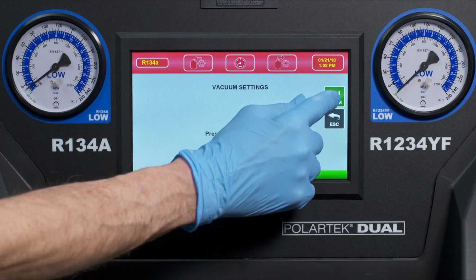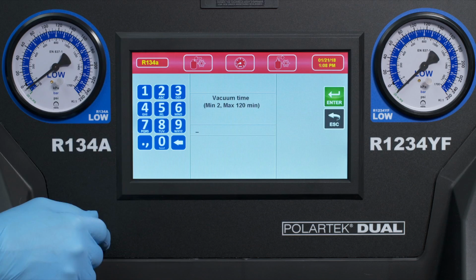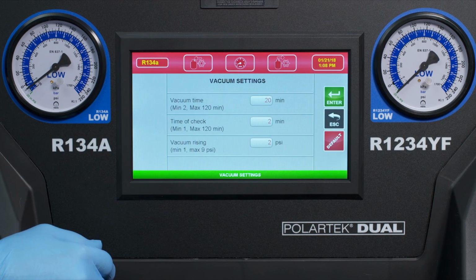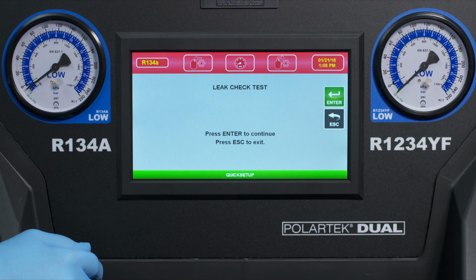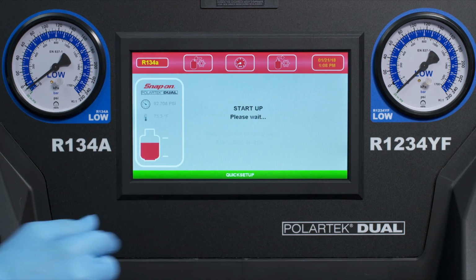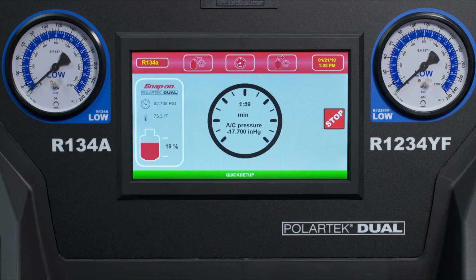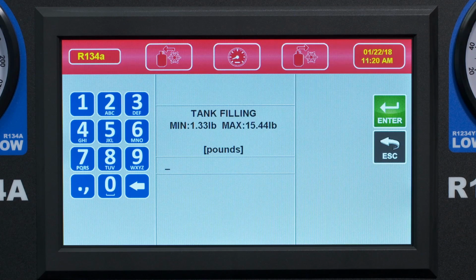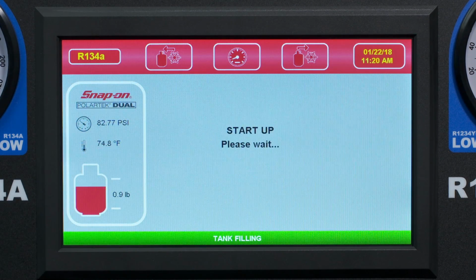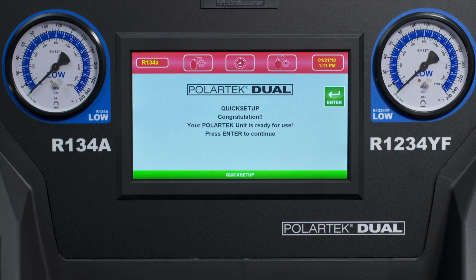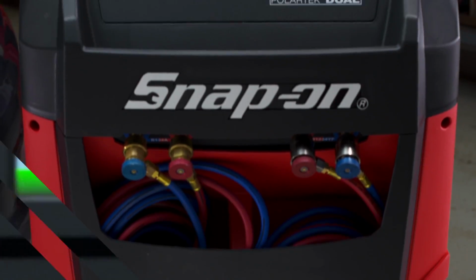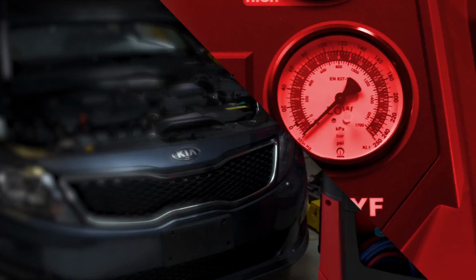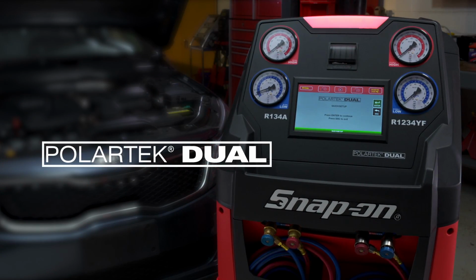Next, the default vehicle vacuum settings will appear. Change the default values if preferred. Press Enter. The machine will then perform a leak check integrity test. This can take several minutes. Upon completion of the leak check test, you'll be prompted to start the tank filling process. When the process is finished, Quick Setup is now complete. Congratulations! Your Polartek Dual AC recycler is set up and ready for use.